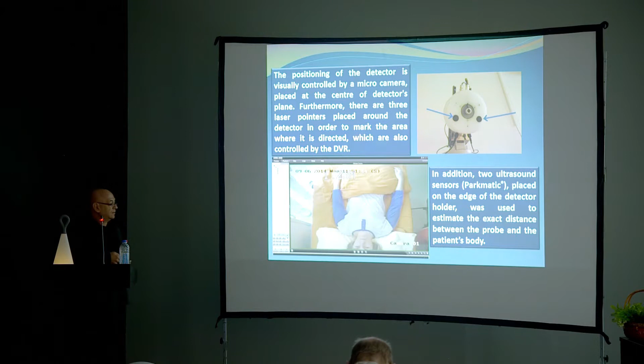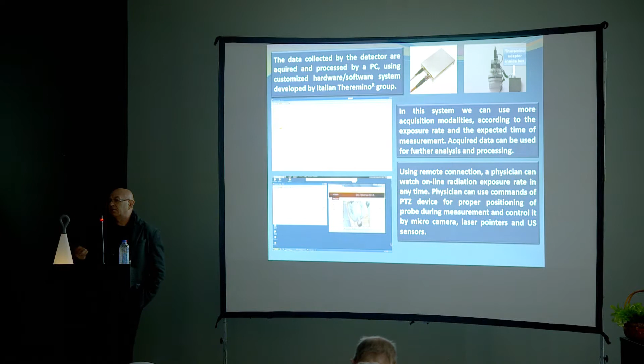All data collected by the probe we use for further analysis by a system developed by the Theremino group as an interface between the probe and a personal computer, which is able to register the actual count rate, counts per minute or counts per second from the patient's body, and the exposure rate from the patient's body at this moment. We can see it numerically and graphically for a longer period of acquisition.